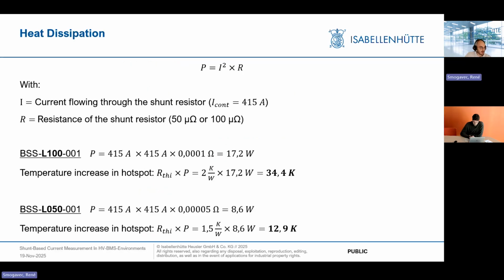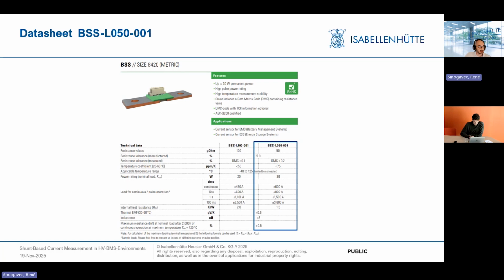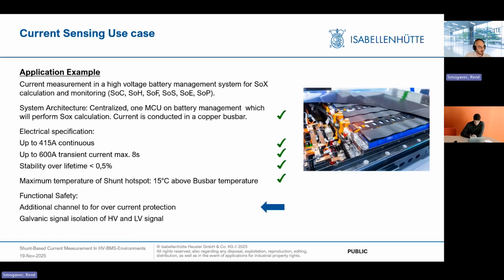And the calculation is as simple as U equals R times I to calculate that. So if you have the 100 microohm, you just calculate the power that you get with using this resistance value and the RTHI to get the 34.4 Kelvin, which is too high because we have just 15 degrees Celsius left. With the 50 microohm, we end up with 12.9. So the result is we use the BSS analog shunt with 50 microohm.